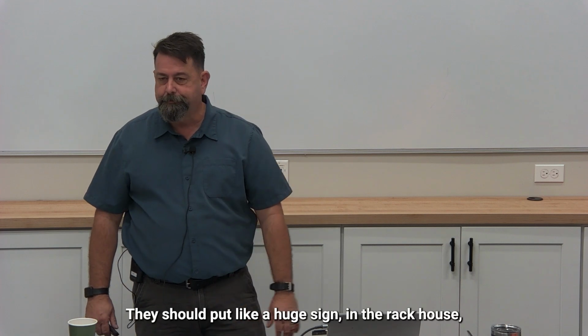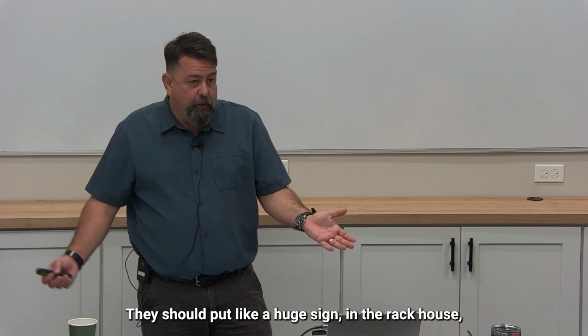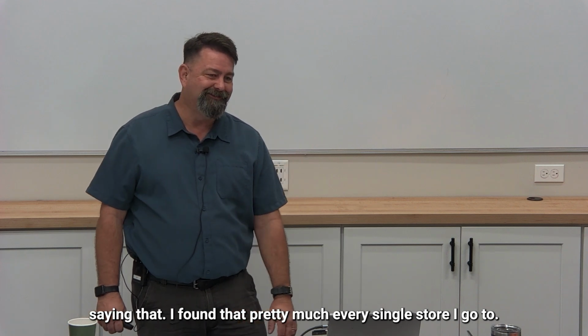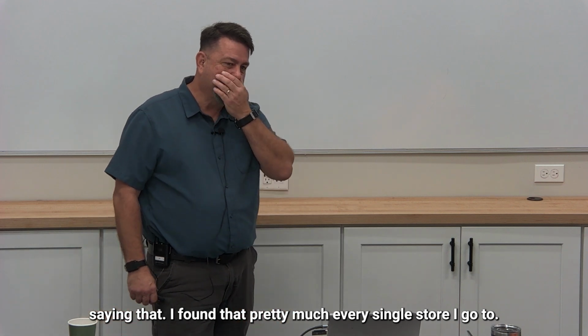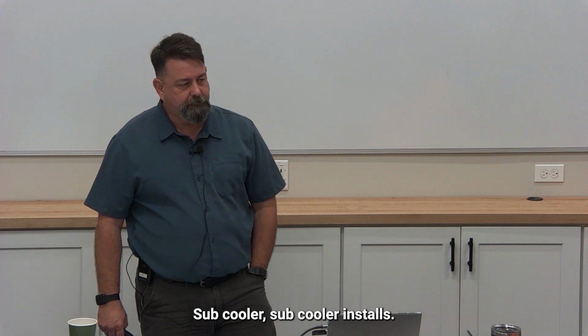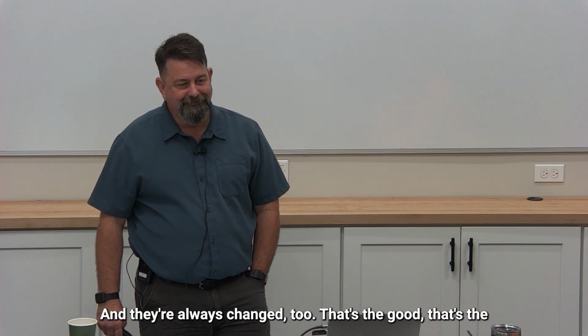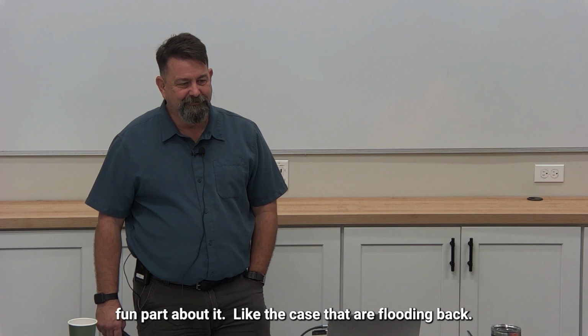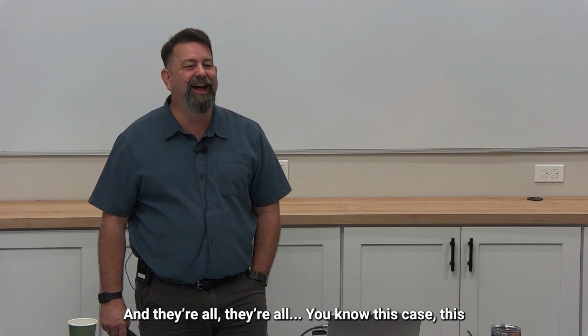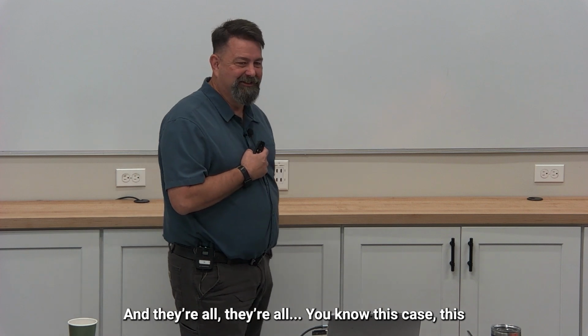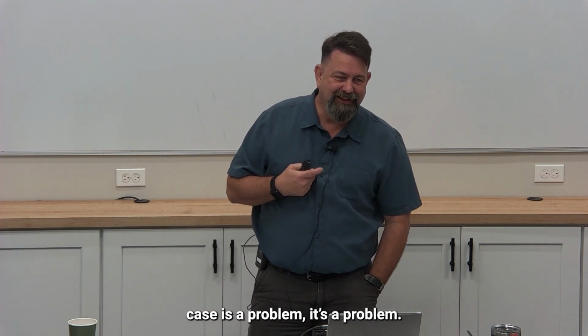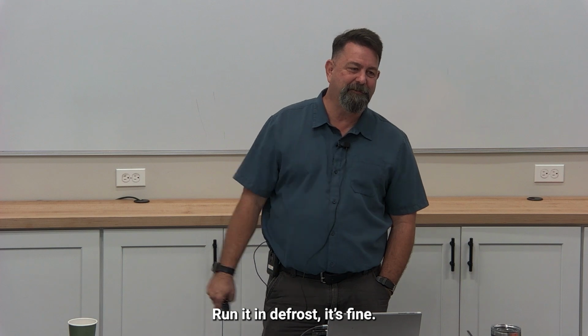They should put a huge sign in the rack house warning about that. I've found that at pretty much every single store I go to, it happens all the time with subcooler installs, and the valves are always changed too. That's the fun part about cases flooding back, the valve is always new, and it just gets put in scope as a case problem, the TXV's a problem, change it, run it in defrost, it's fine. Yeah, so that's a lack of education, and that's why we're talking about it today.